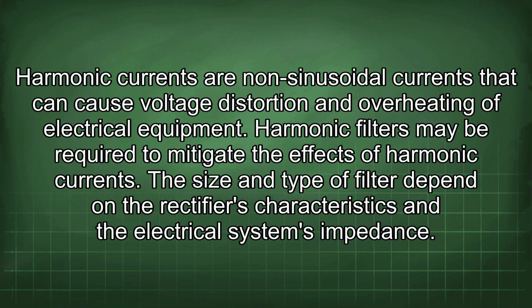Harmonic currents are non-sinusoidal currents that can cause voltage distortion and overheating of electrical equipment. Harmonic filters may be required to mitigate the effects of harmonic currents. The size and type of filter depend on the rectifier's characteristics and the electrical system's impedance.